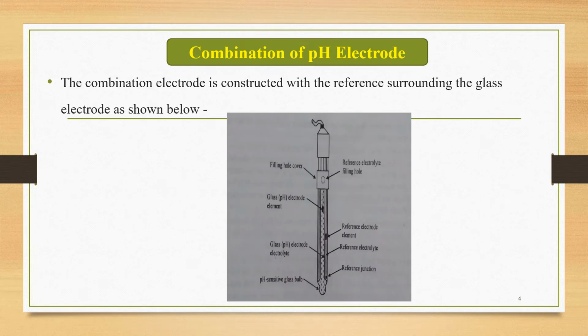Now, how is this combination electrode constructed? The combination electrode is constructed with the reference surrounding the glass electrode as shown below. This is a construction figure for this combination electrode. In this case, two types of electrodes, the glass and the reference, are combined together. In the bottom part of this combined electrode, there is a pH sensitive glass bulb. This is a pH sensitive glass bulb. It is very important as far as the measurement of pH is concerned.